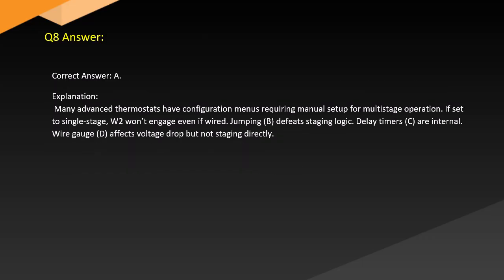Answer. Correct answer: A. Explanation: Many advanced thermostats have configuration menus requiring manual setup for multi-stage operation. If set to single-stage, second stage won't engage even if wired. Jumper, B, defeats staging logic. Delay timers, C, are internal. Wire gauge, D, affects voltage drop but not staging directly.